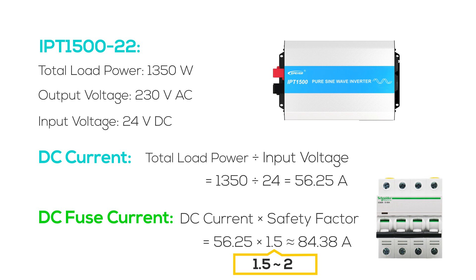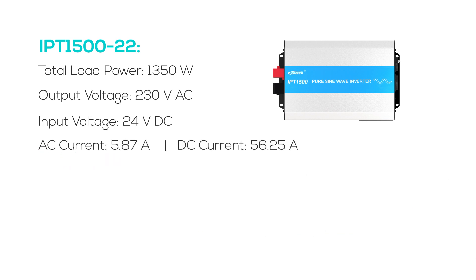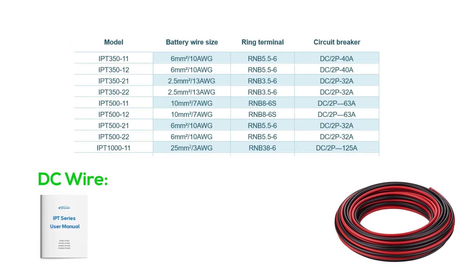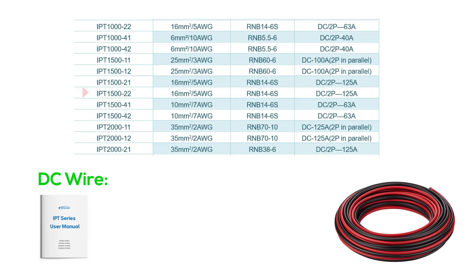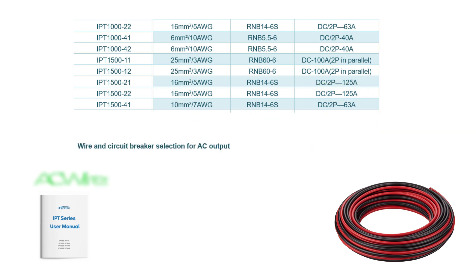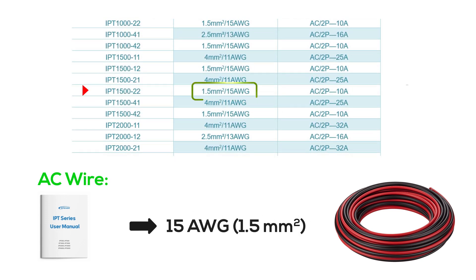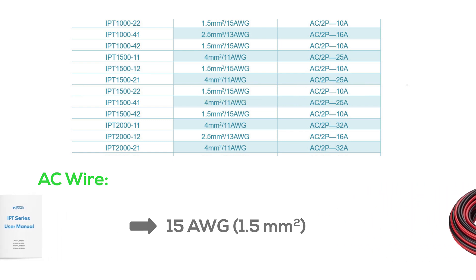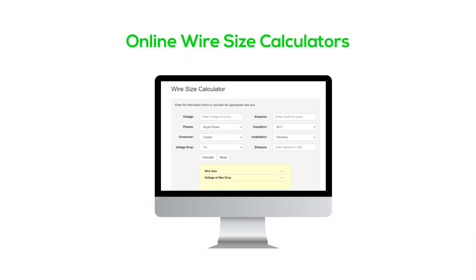For the DC fuse, the closest value higher than 84.38 amperes is acceptable. Lastly, for wire sizing according to the IPT manual for the IPT 1522: on the DC side, a 5 AWG or 16 square millimeter wire with an RNB 14-6S ring terminal and a DC 2-pole 125-ampere fuse is recommended. On the AC side, a 15 AWG or approximately 1.5 square millimeter wire with an AC 2-pole 10-ampere fuse is recommended. An online wire size calculator can also be used, but note it may differ from the manual since the manual offers the maximum wire size needed.